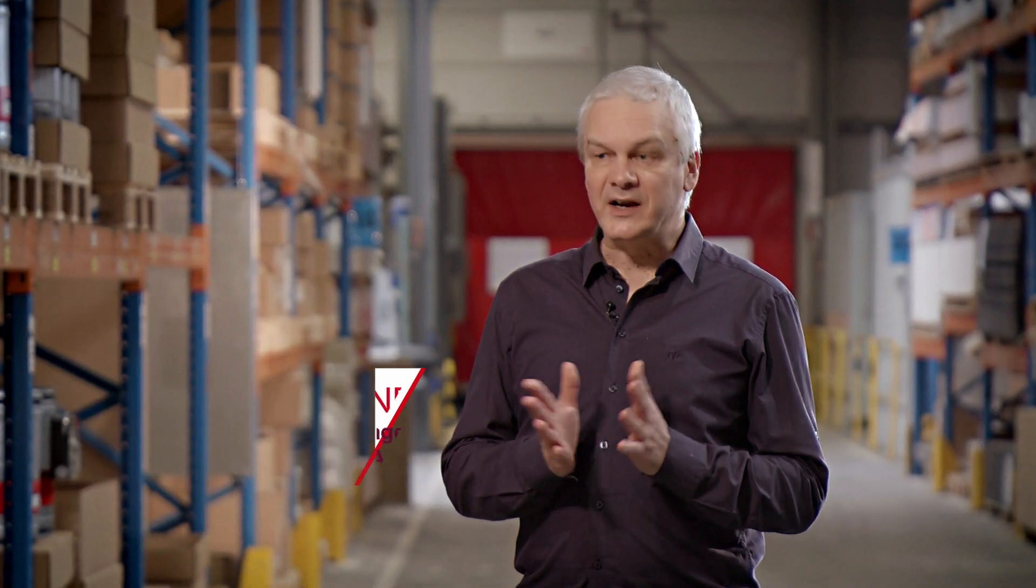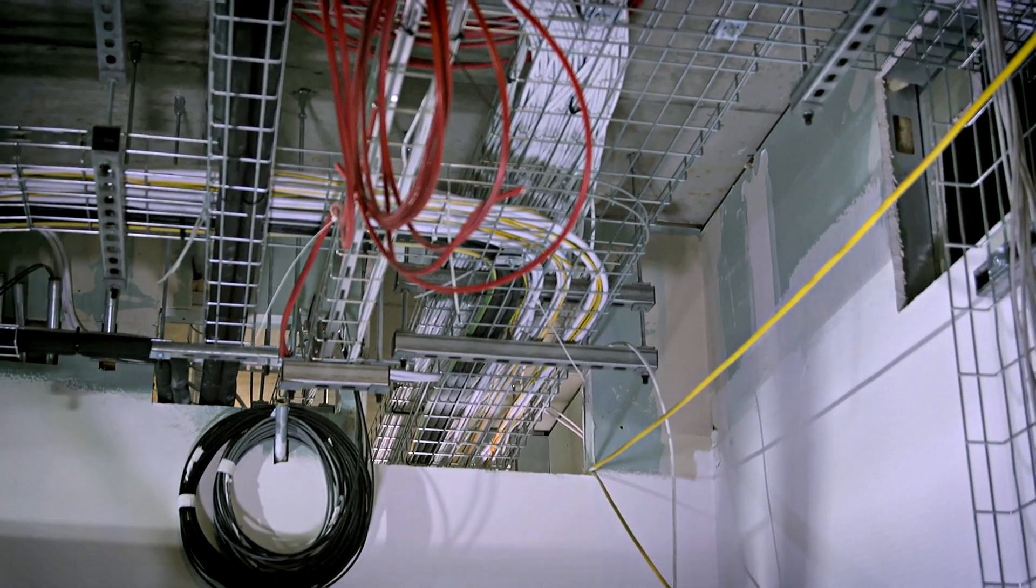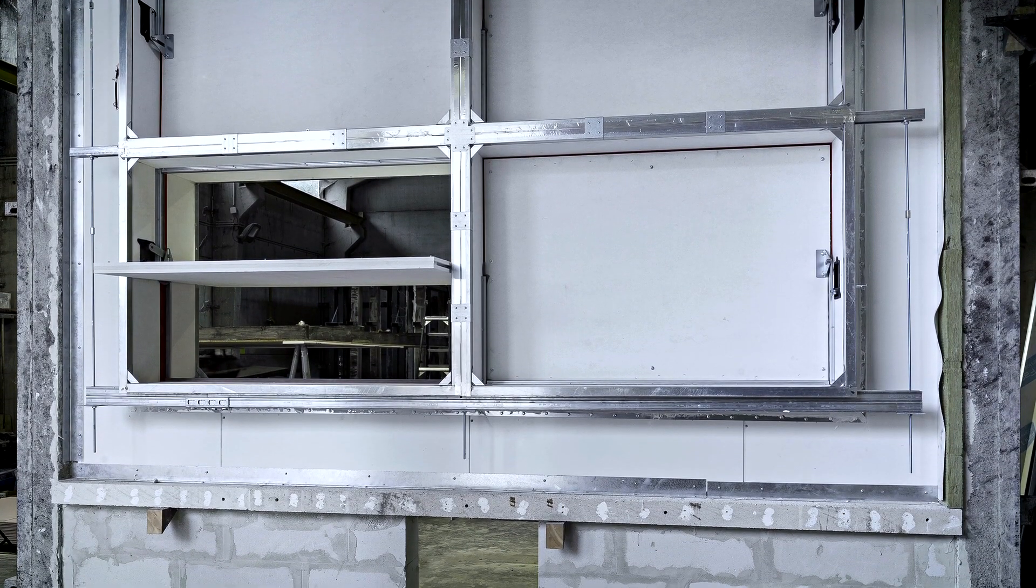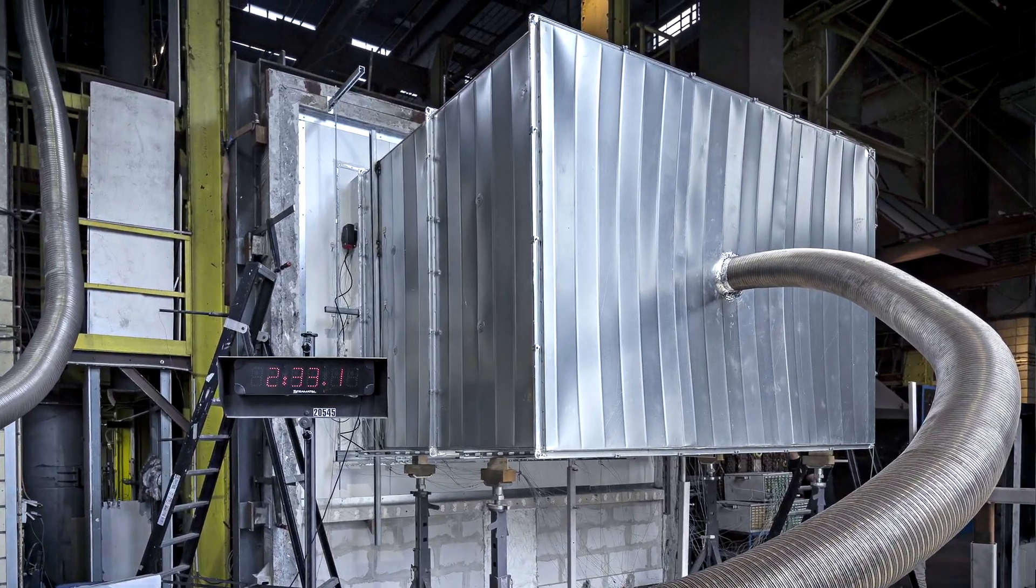The big challenge for the designers involved is to cope with the tight spaces where all services have to pass through. Fire dampers are particularly difficult. You have to do full-scale testing with dampers in that wall type.